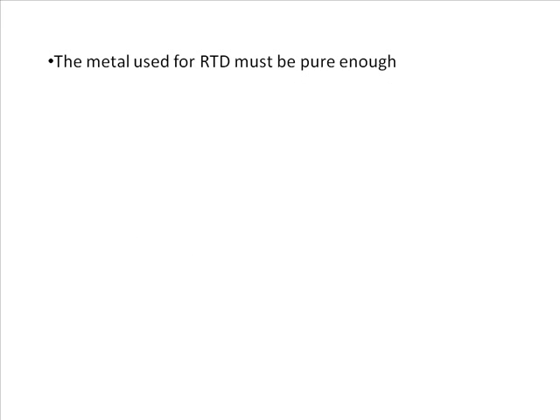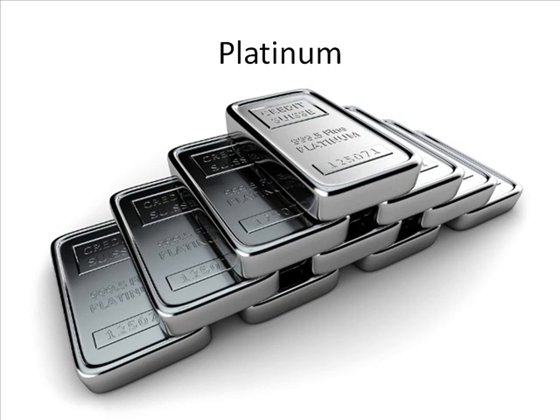The metal used for RTD must be pure enough, otherwise resistance temperature characteristics of the metal deviates from its original graph and consequently the temperature measurement would be erroneous. If platinum is used as the sensor of RTD, then purity of the platinum must be checked first before using it in the instrument.